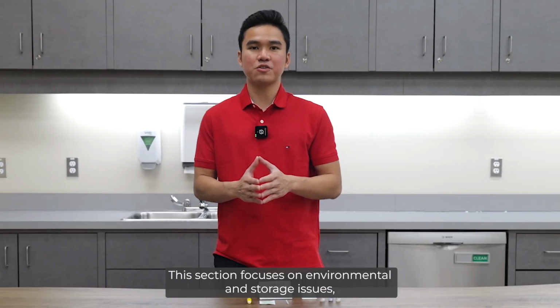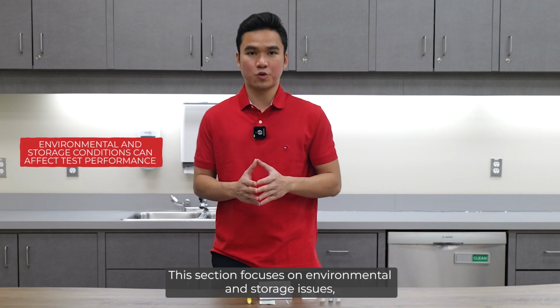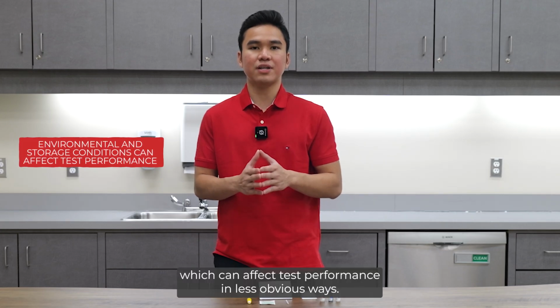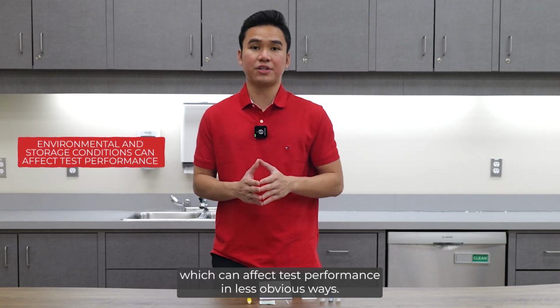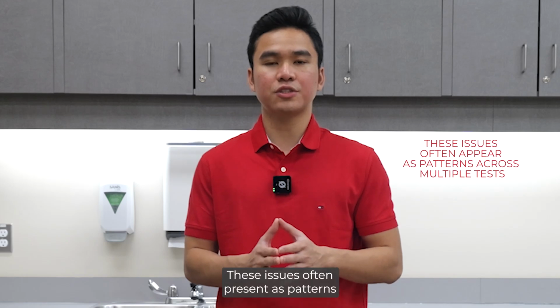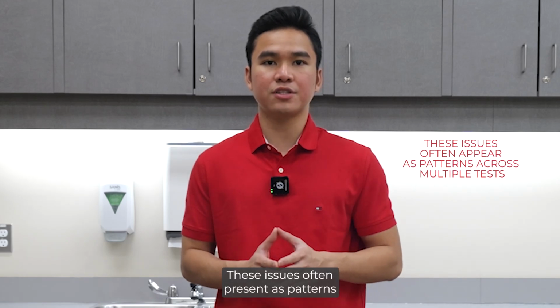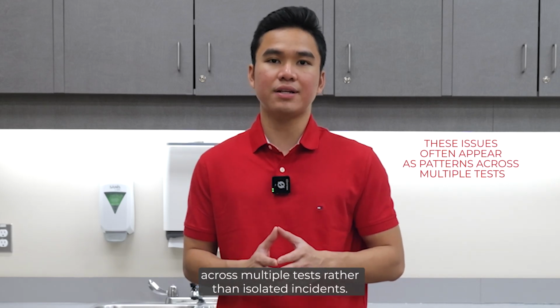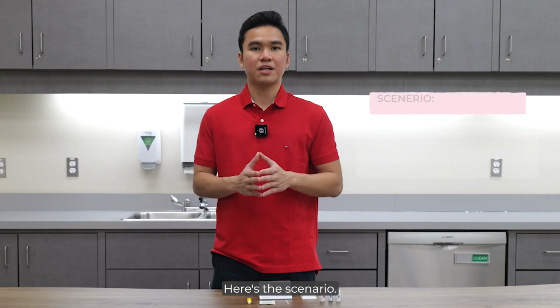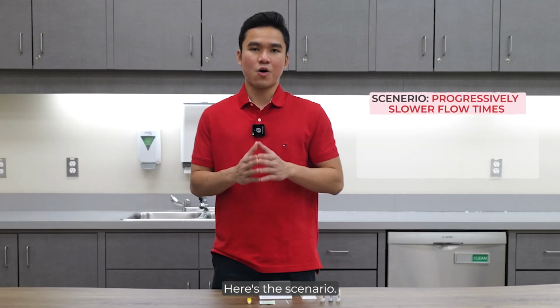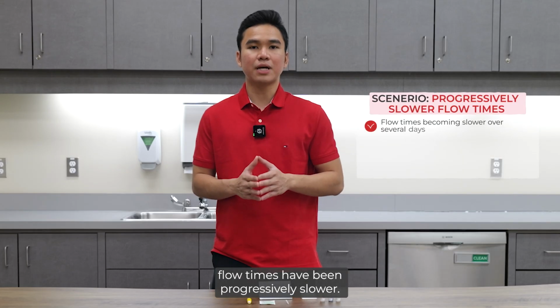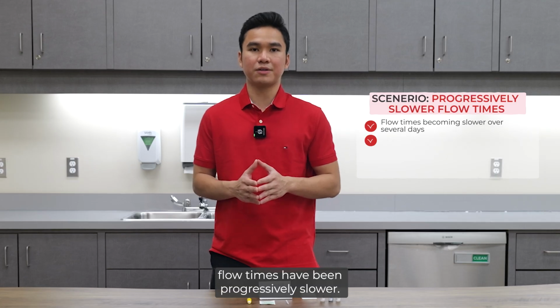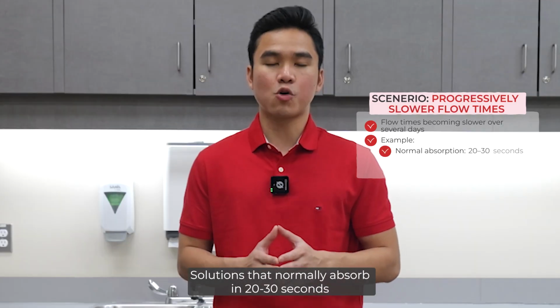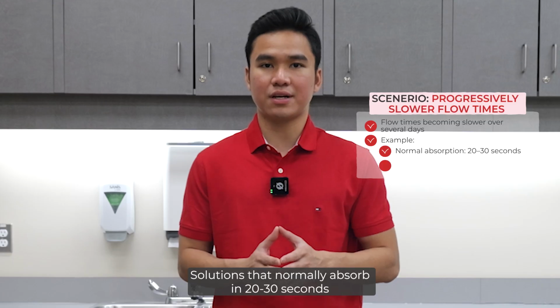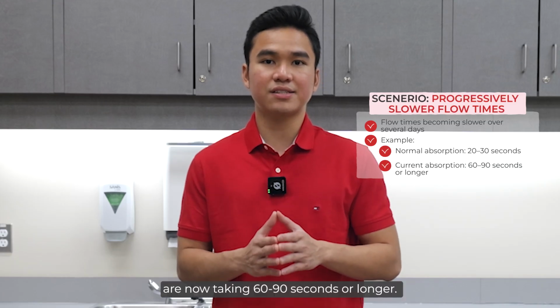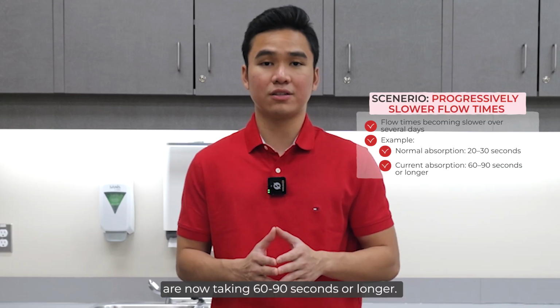This section focuses on environmental and storage issues, which can affect test performance in less obvious ways. These issues often present as patterns across multiple tests rather than isolated incidents. Here's a scenario. Over the past week, flow times have been progressively slower. Solutions that normally absorb in 20 to 30 seconds are now taking 60 to 90 seconds or longer.